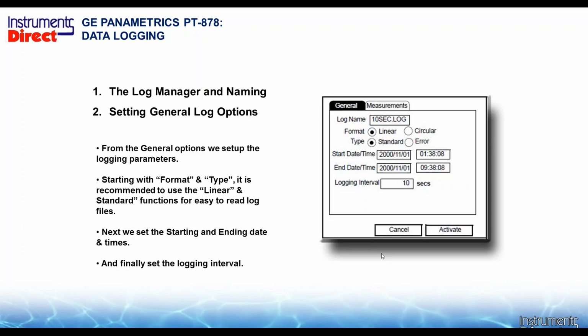In this case there, we need to format and type. In this case, we're going to use linear standard functions, and this is easy read to the log file, and that's pretty much your default. So next, we're going to set the start and end time there. So here, you notice I've got year, month, date, and in this case there, I need to have a start time and a start date. Give yourself some time to start the log there, not a few seconds there, because if you start the log after this, you may be sitting there with no log data.